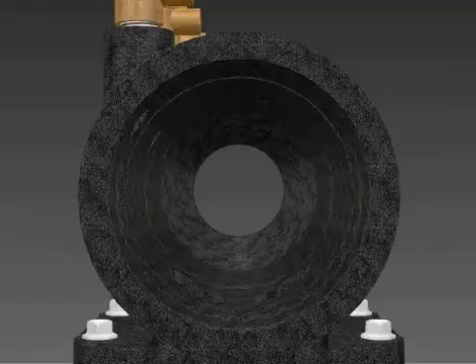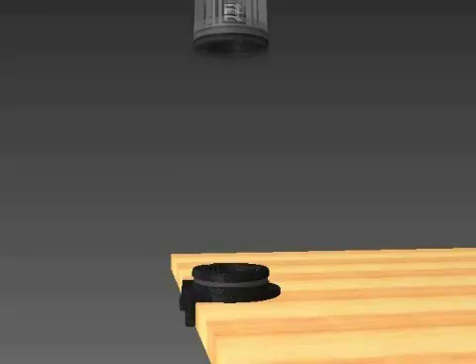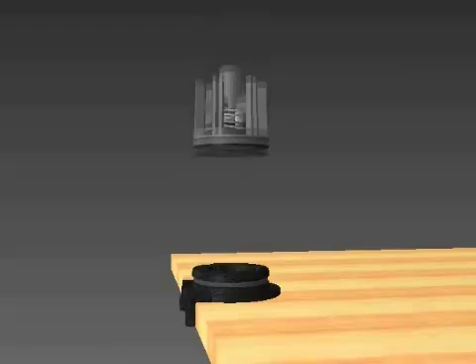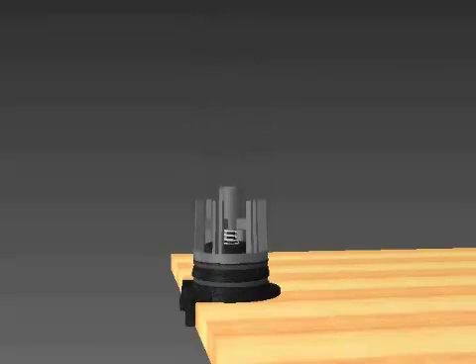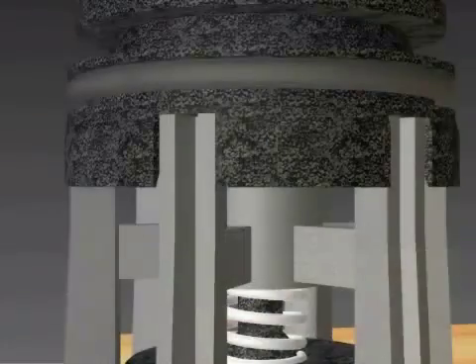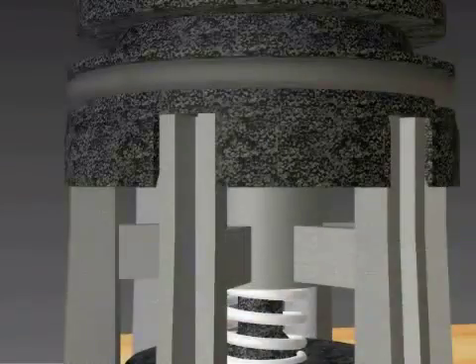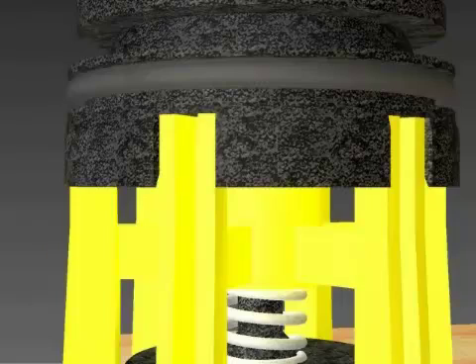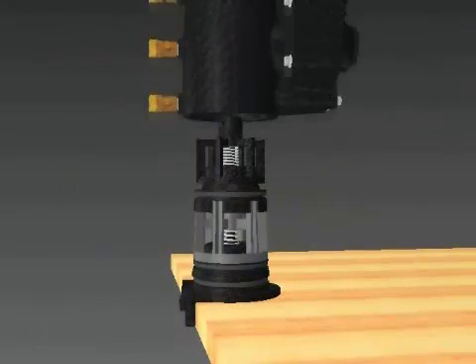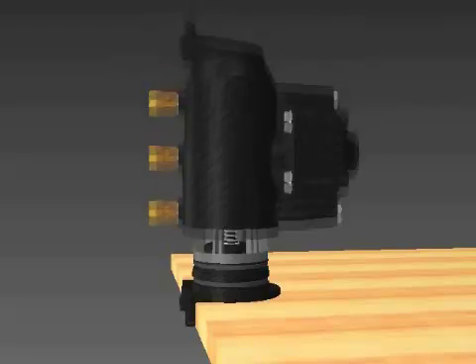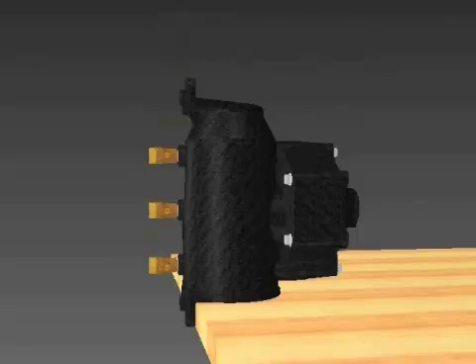Wipe clean and inspect the inside of the housing. Place the sleeve on a flat surface with the bolt tab hanging off the edge. Stack the number one check and then the number two check on top of the sleeve. Make sure to line up the notches in the number two check with the number one spring retainer. Place the housing onto the checks and the sleeve. Push down on the housing with a rocking motion to seat all of the O-rings into the housing.